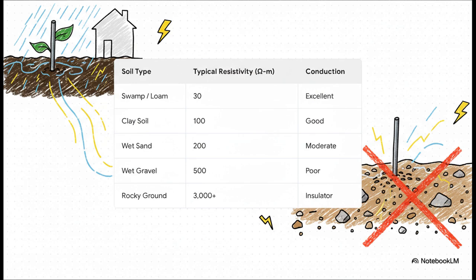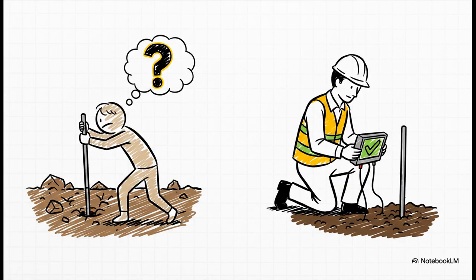The effectiveness of your grounding system depends entirely on the type of soil around your house. Wet, clay soil is a great conductor, but dry, rocky ground is practically an electrical insulator. This means you can't just stick a metal rod in the ground and hope for the best. It's this extreme variability that means you can't just install a grounding system and assume it's safe. It has to be professionally measured with special equipment to verify that its connection to the earth is strong enough to do its job.